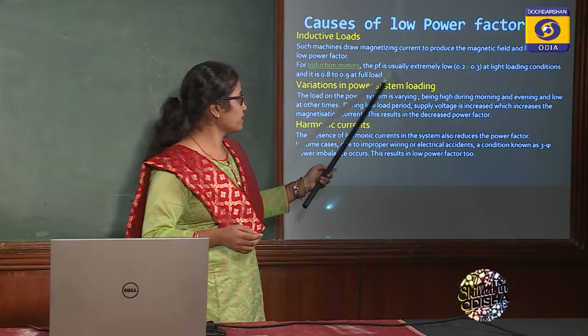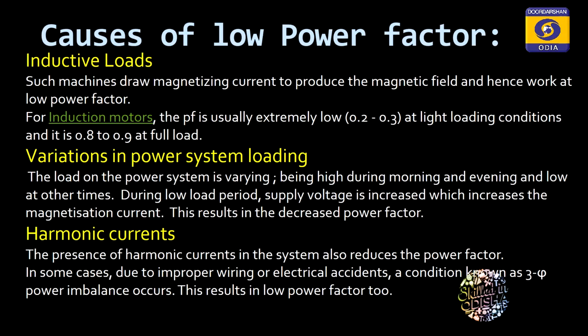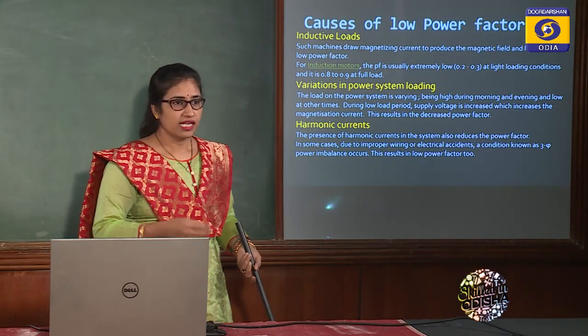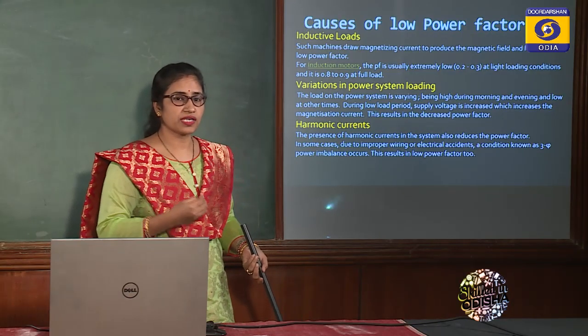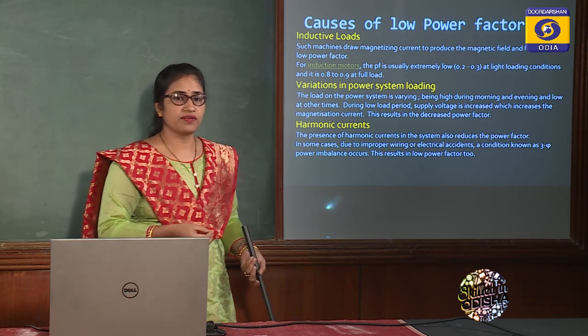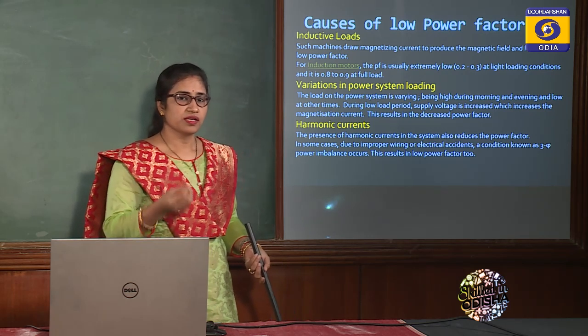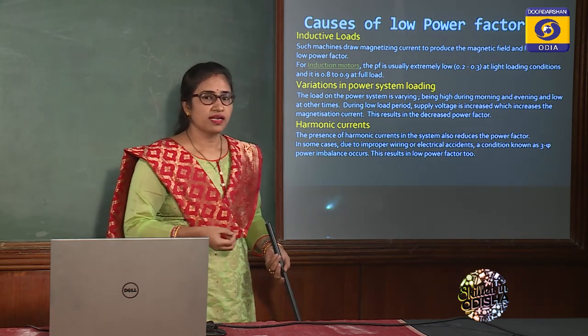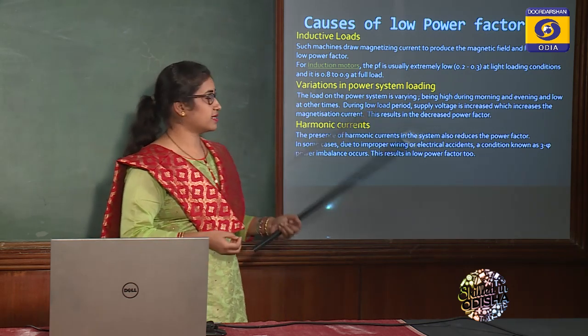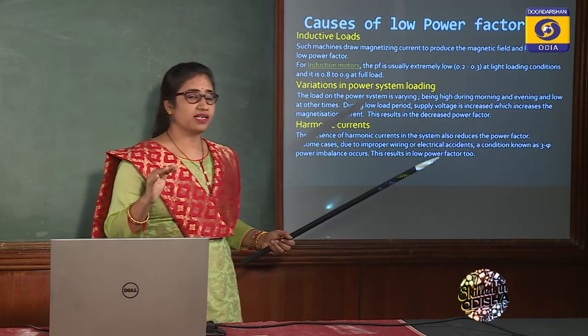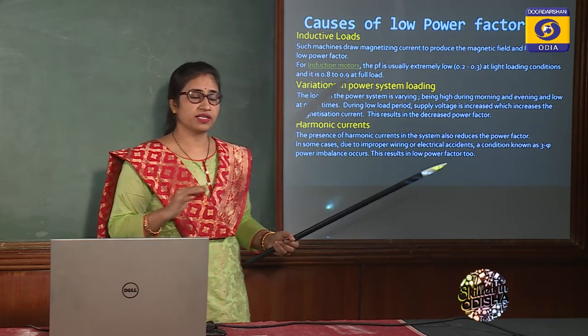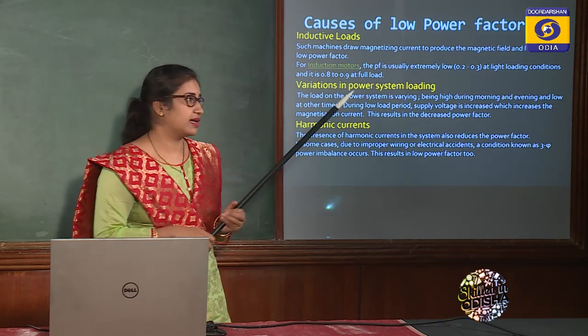The power factor is usually extremely low — around 0.2 to 0.3 — at light loading conditions. When the motor is operating at full load, the power factor is maintained between 0.8 to 0.9. It is desirable to work at full load to maintain a good power factor.